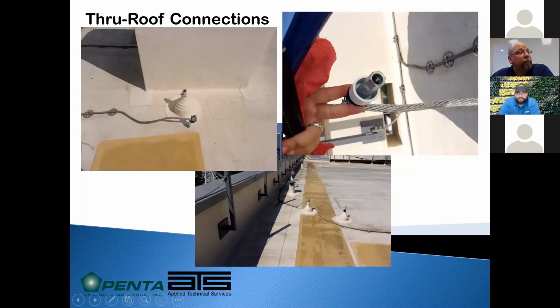We've seen many times where you have a beautiful rooftop system. In building construction, a lot of times an electrical contractor is hired by the general and they do everything inside the building. They do the grounding at the base of the building. They route all the cabling up through the building. And in this case, just on the underside of the roof, the down conductors were routed by the electrical contractor and they exited just under the roof from this column line.